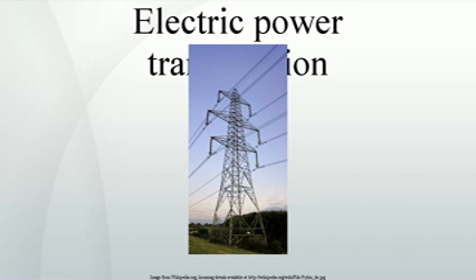Losses. Transmitting electricity at high voltage reduces the fraction of energy lost to resistance, which varies depending on the specific conductors, the current flowing, and the length of the transmission line. For example, a 100-mile 765 kV line carrying 1000 MW of power can have losses of 1.1% to 0.5%. A 345 kV line carrying the same load across the same distance has losses of 4.2%.